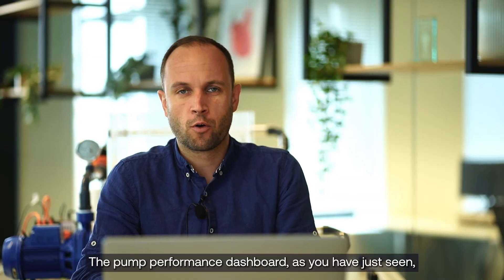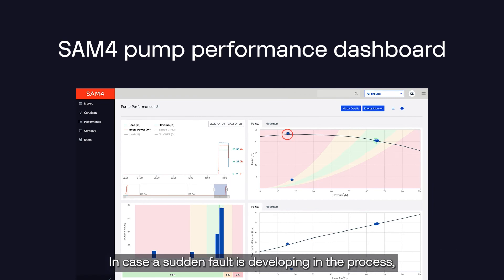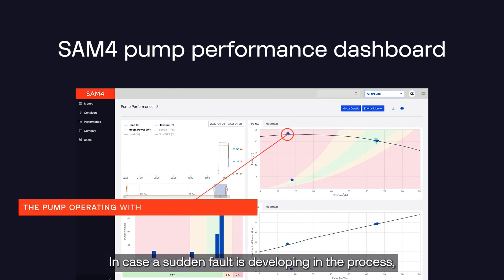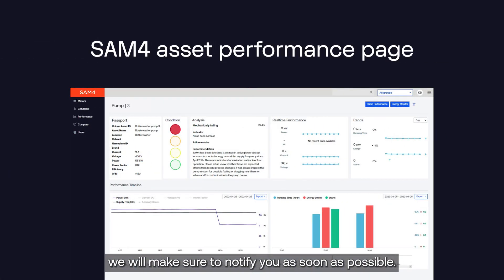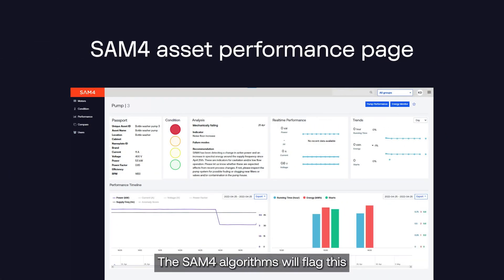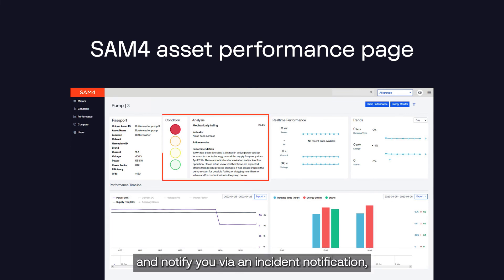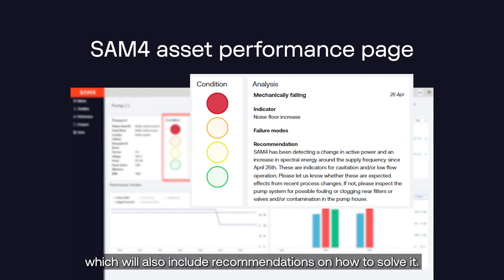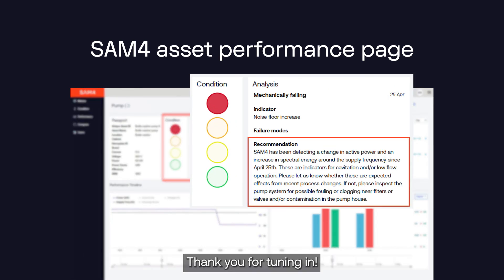The pump performance dashboard allows you to view how the pump is operating. In case a sudden fault is developing in the process, like this low flow cavitation example, we will make sure to notify you as soon as possible. The SAM4 algorithms will flag this based on the current and voltage measurements and notify you via an incident notification, which will also include recommendations on how to solve it. Thank you for tuning in.